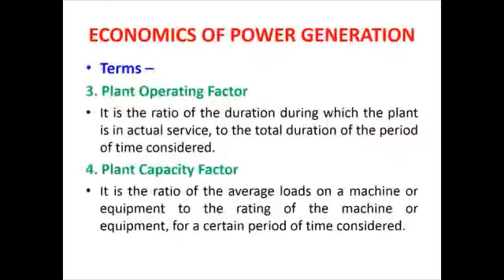Then third, plant operating factor. It is the ratio of the duration during which the plant is in actual service to the total duration of the period of time considered. So while calculating plant operating factor, we take only the hours or duration for which the plant has been running, relative to the total duration of the period considered. For example, if 12 months is the duration considered, and out of the 12 months the plant is in operation for only 9 months, then it will be the ratio of 9 to 12.